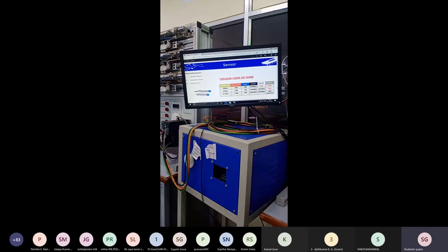Okay, sensors used in PLC programming or in automation have some different color codes. For a three wire sensor, the red or brown wire is positive, blue is negative, and black is the NO contact output wire.